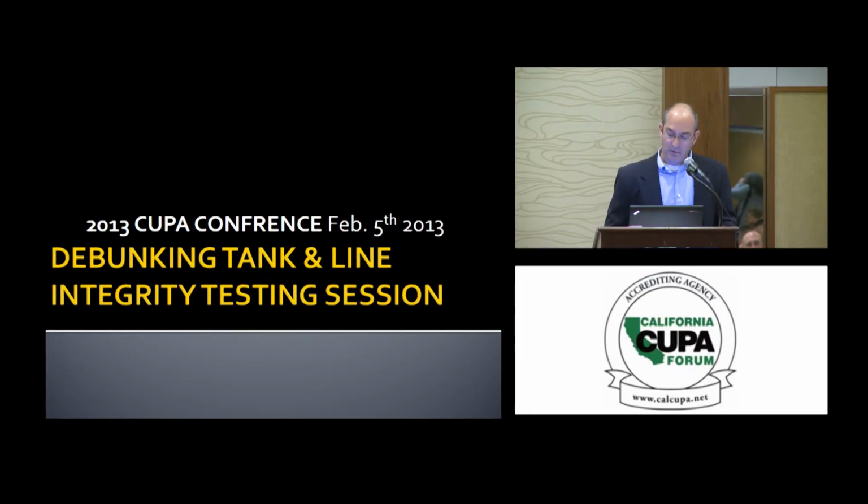The cylinder is filled with fuel. You can see there's a fuel can here and a funnel. This top portion of the tester actually has a reservoir with some fuel that can be drained down into the test apparatus used to apply fuel to the line. Once the line is filled up with fuel and the pressure is applied, then the technician monitors the change in level, and he records that data manually just on a clipboard. Here's a close-up to see a little bit better view of what he's looking at there.